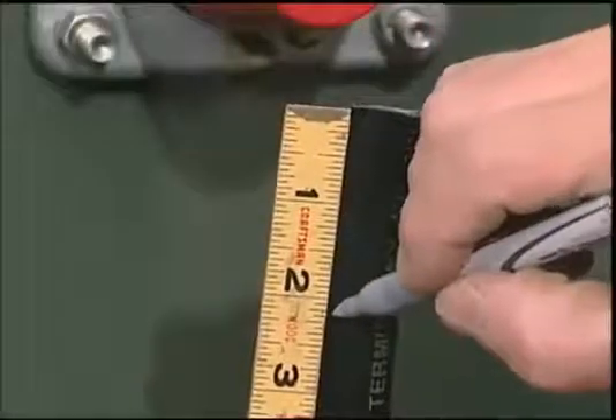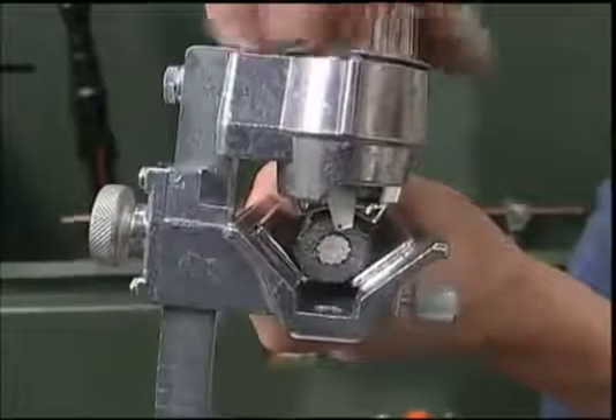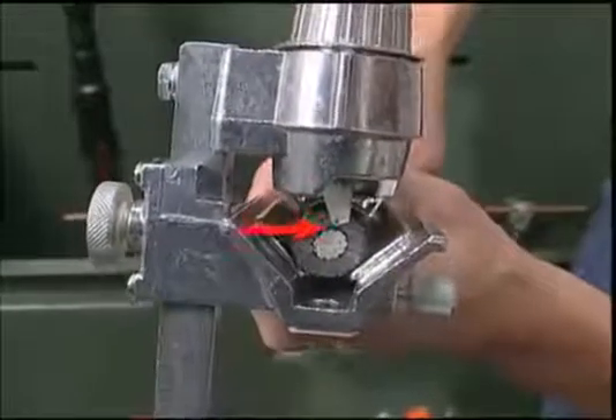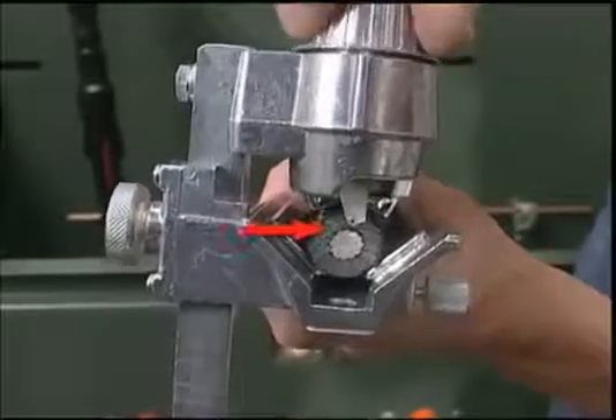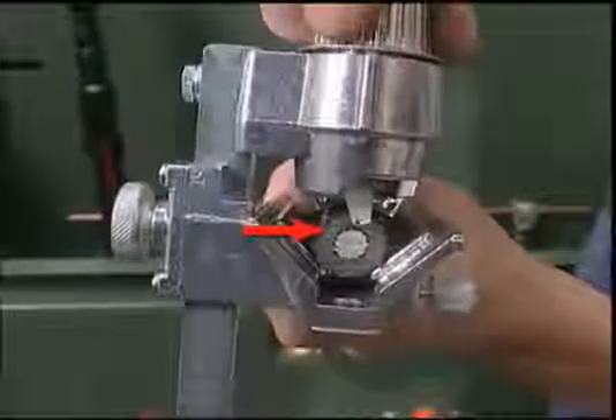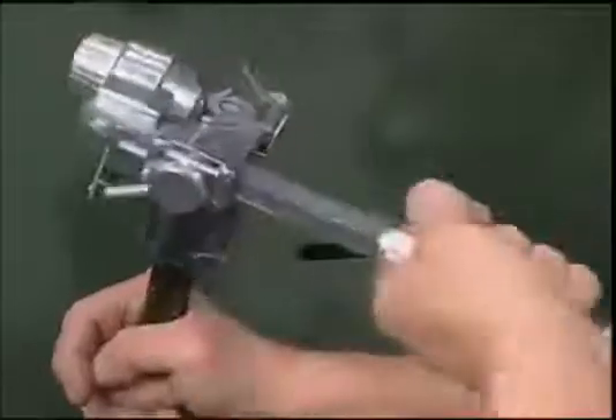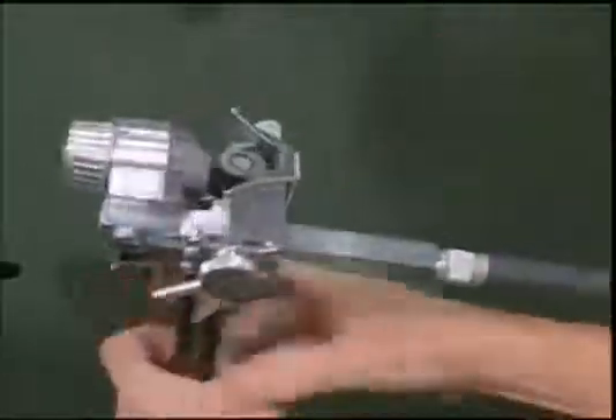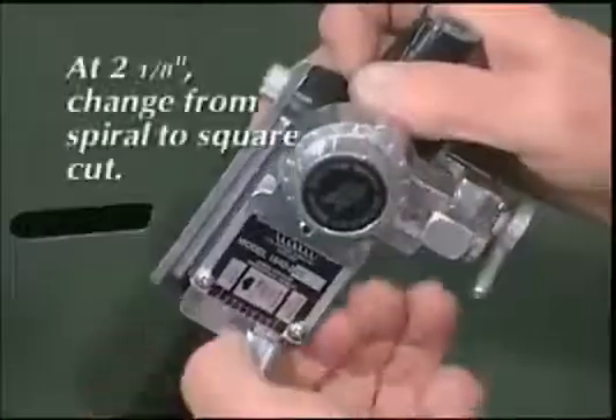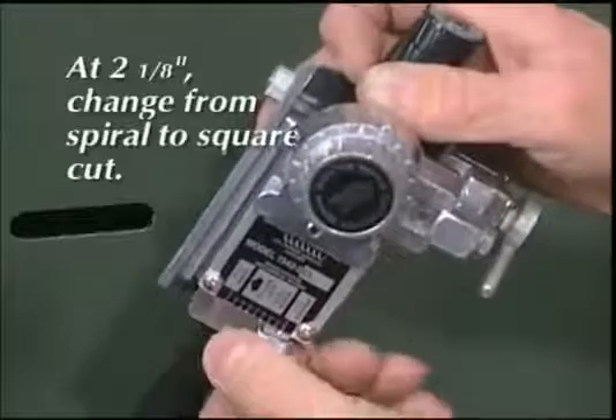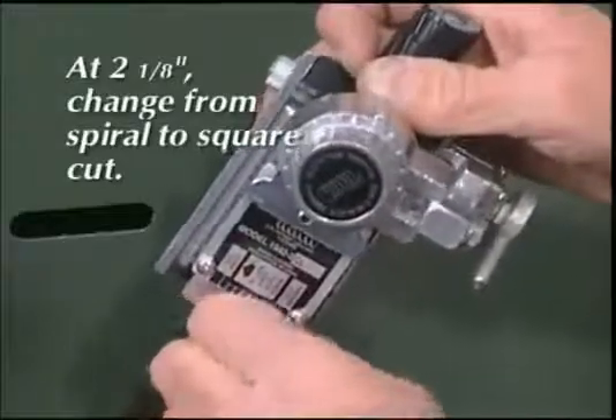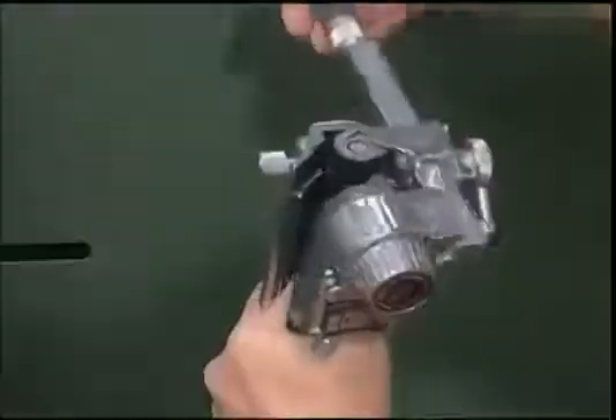Now measure 2 1/8 inches from the end of the cable. Place the insulation removal tool onto the cable end and adjust the depth of the cut so that it removes all of the insulation without nicking the conductor. Once the depth is adjusted properly, proceed with insulation removal. Upon reaching the 2 1/8 inch measurement, change the tool setting from spiral cut to square cut. Finish cutting and remove the tool.